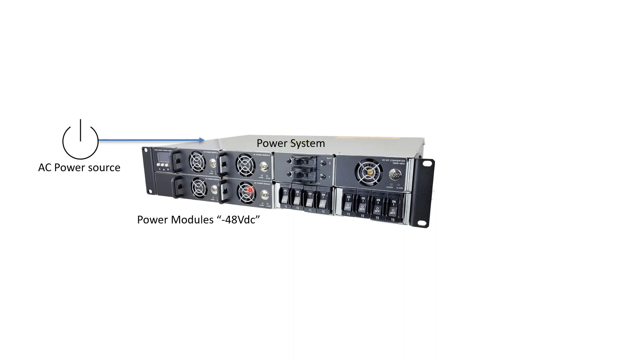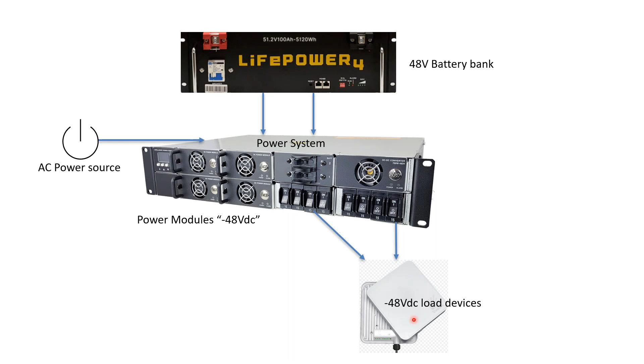They are 48 volts and connected into a negative voltage system, meaning the positive is grounded. So we can power minus 48 volt loads from the integrated load distribution. There is a DC-DC converter here, 700 watts, which converts 48 volts to 24 in this case.